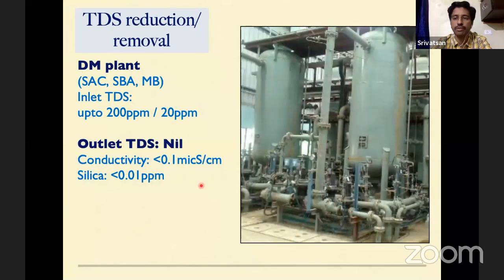The next stage, now we have reduced the TDS level to 20 ppm. Now we have a conventional demineralization plant which has cation resins and anion resins present in these vessels, which absorb all the salts present in water. We can have a high concentration limit of up to 200 ppm, above which we may typically need a RO system upstream of this system to have an optimum outlet water quality.